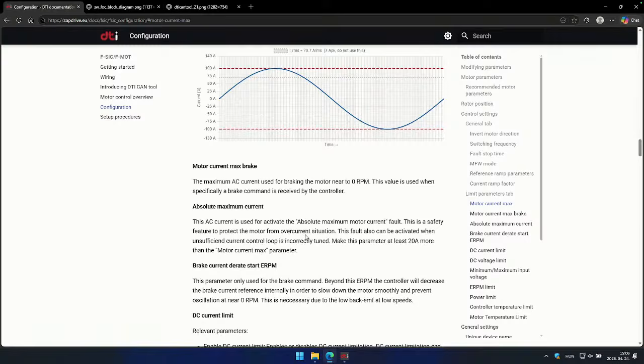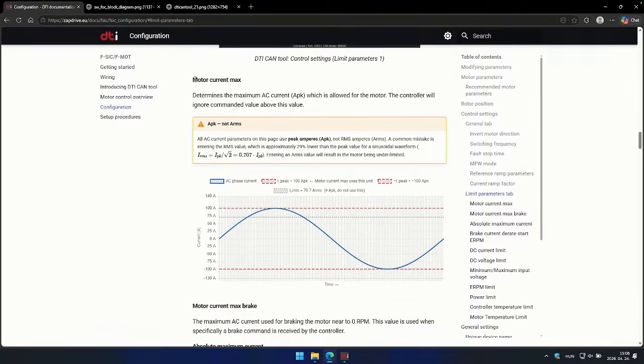What is very important here is that the motor current max and any other AC current related parameters are understood in peak dimensions, which means ampere peaks, and not RMS currents. So it identifies the sine peak, the amplitude of the sine, and not the RMS value. So you have to type A peak, because if you type RMS, then you have approximately 29% lower value than the peak. So just be careful about that.